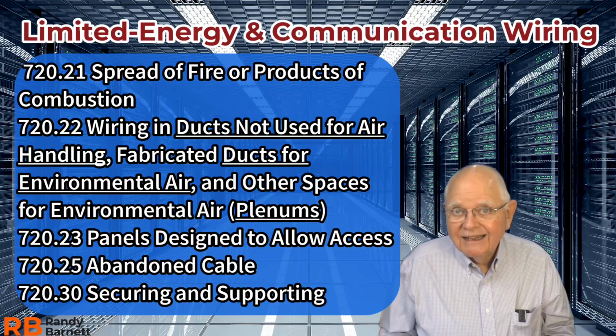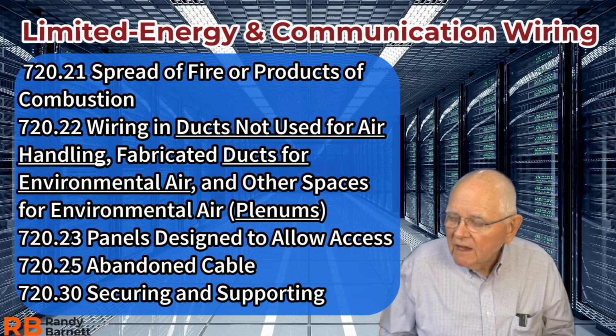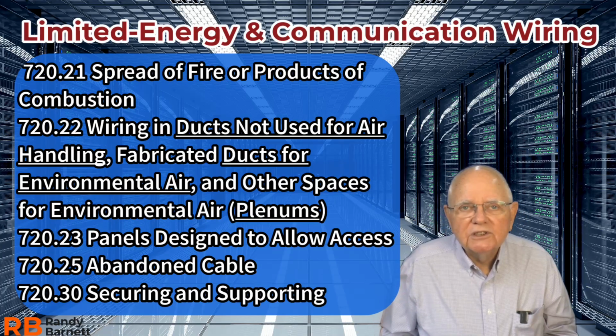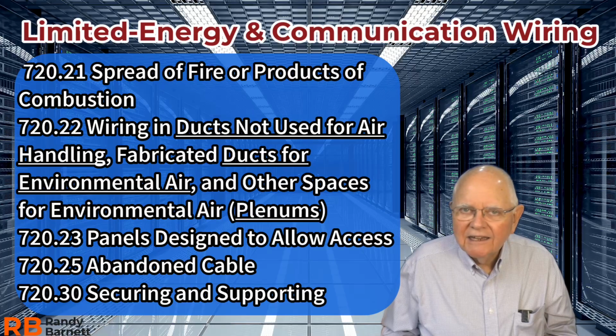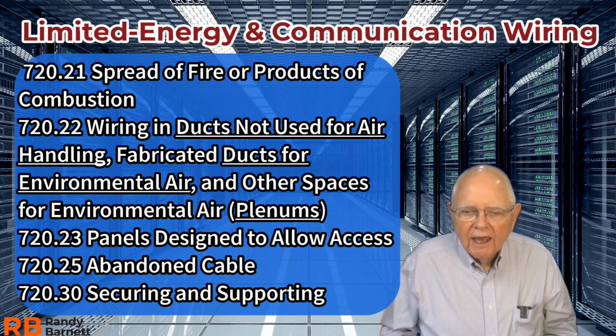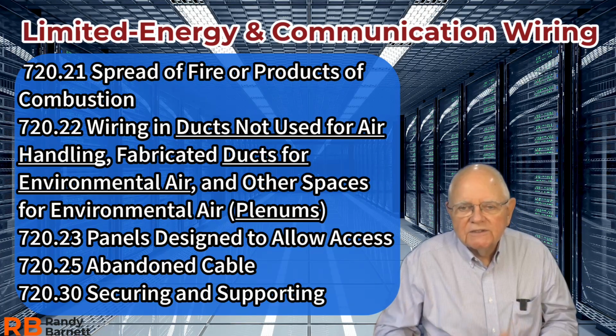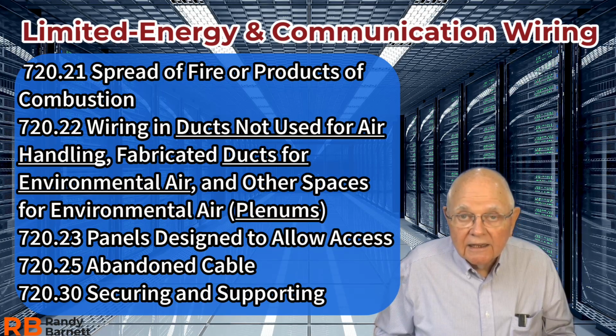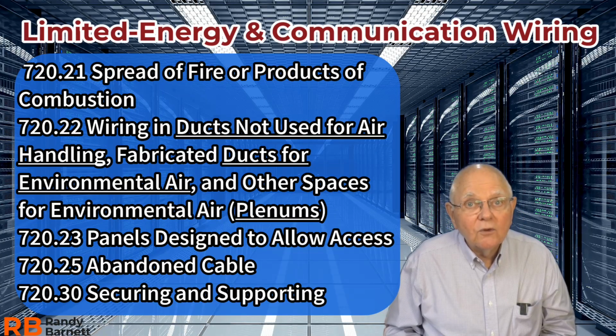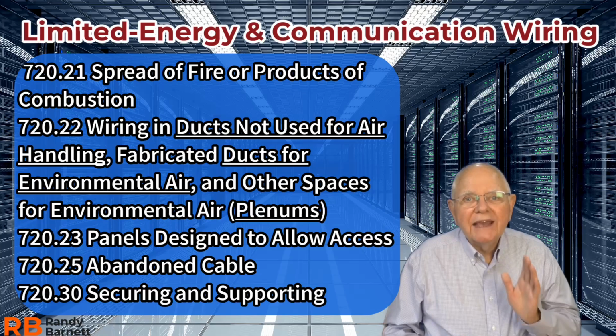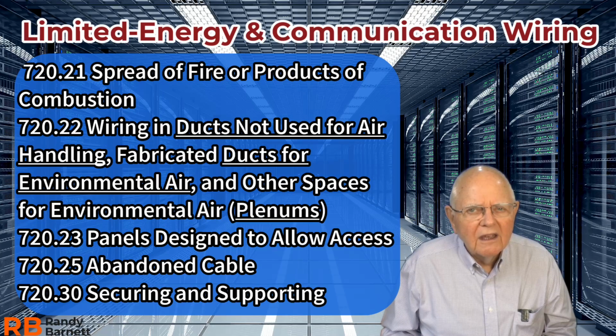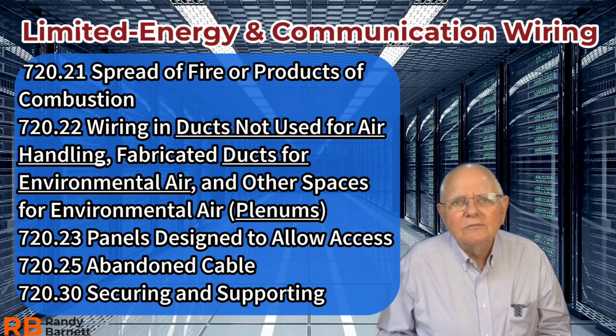Now, let's talk about that tagging for future use. Certainly legitimate to do that. It does not mean I take a piece of white electrical tape and write on there with a Sharpie, it says future use, something like that. It tells me in 720.25 that that tag must be able to withstand the environment. So I need the right tag on that cable.